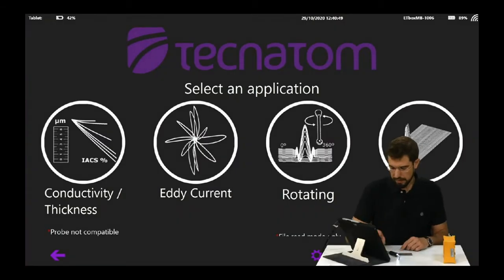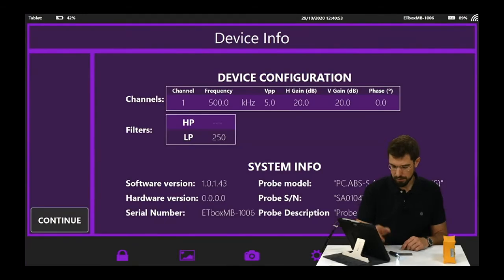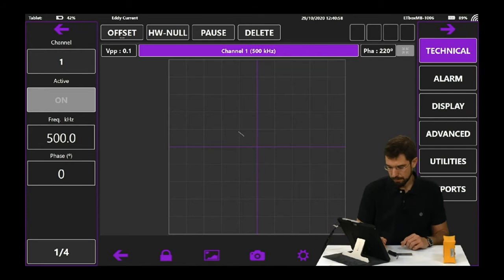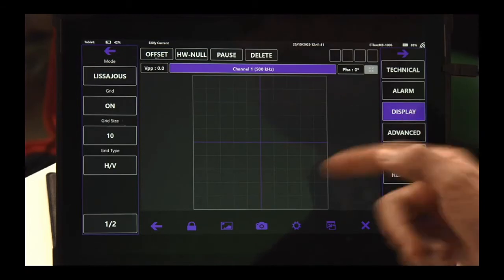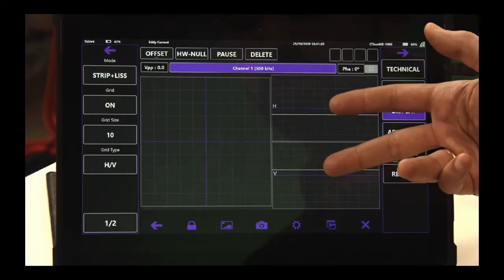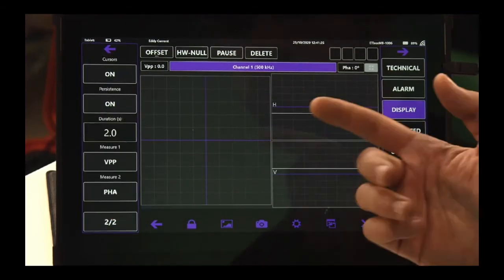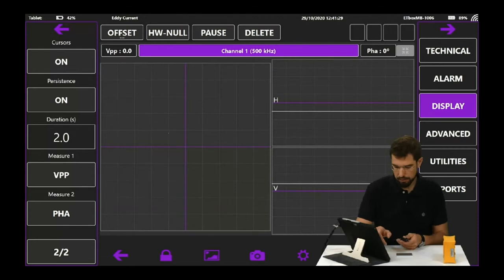We're going to start the eddy current application. It identifies our probe right away. Okay, so in this case, we've already seen the distribution of the screen. Let's configure the display the way we want it to perform our inspection. For that, we'll go to the display menu where a submenu spreads out. We have a Lissajous open, and we're going to use strip chart with Lissajous. Once we have that part configured, we can also see there are several other options among which we can choose.